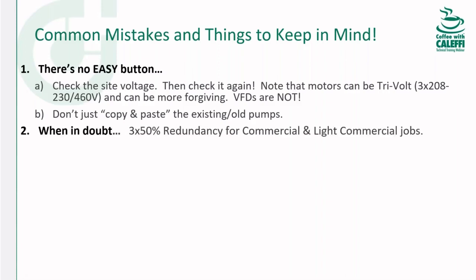I've sized plenty of boosters in my life, and for the most part, everybody needs redundancy. So I always compare two 100% pumps and then three 50% pumps. If it's a big enough system, I'll look at four 33% pumps and so on. I don't know the GPM range, but if it's over 100 to 150 GPM, when in doubt, I would go with three 50% pumps. And again, remember the green and the red shaded areas, that's kind of the reason for that.